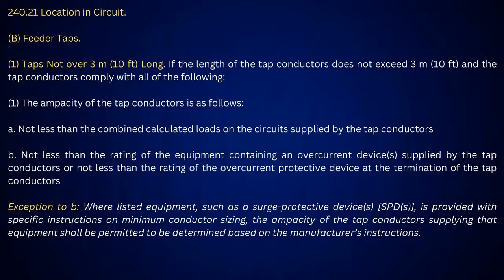And if you have a transformer in the tap, then you've got to get the ratio of the transformer for the secondary part of that calculation. And the primary's done at a third. I'll show all that. But yeah, we ran into a funny thing with that exception, where there was a surge protection device that had number 14 going to it, and it was on a 30 amp.